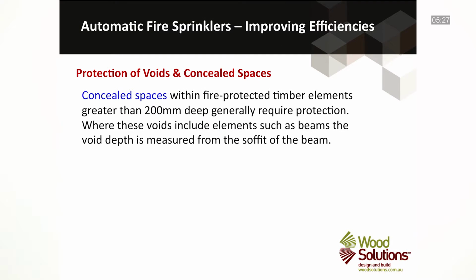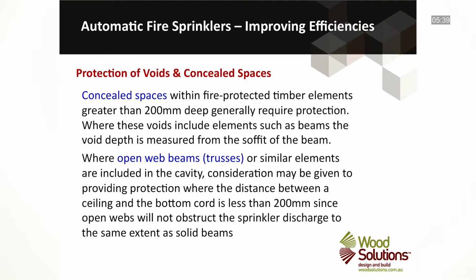Concealed spaces within fire-protected timber elements greater than 200 mm deep generally require protection. Where these voids include elements such as beams, the void depth is measured from the soffit of the beam. Where open web beams, trusses, or similar elements are included in the cavity, consideration may be given to providing protection where the distance between a ceiling and the bottom chord is less than 200 mm, since open webs will not obstruct the sprinkler discharge to the same extent as solid beams.